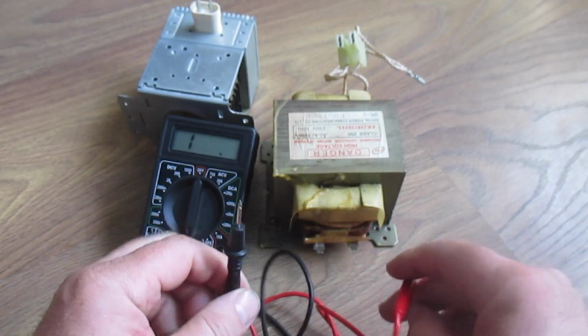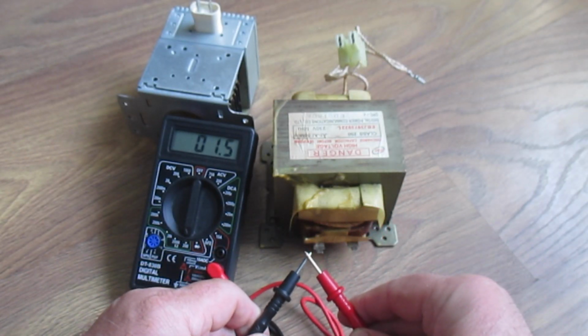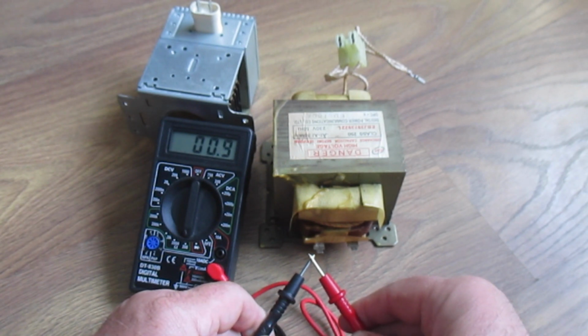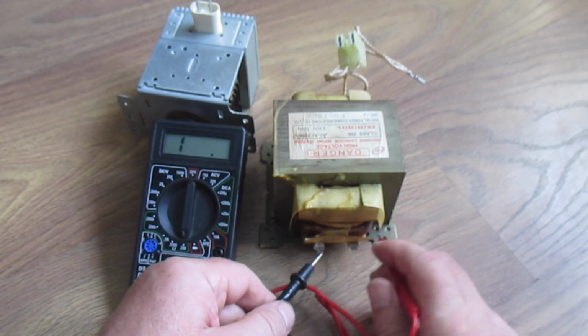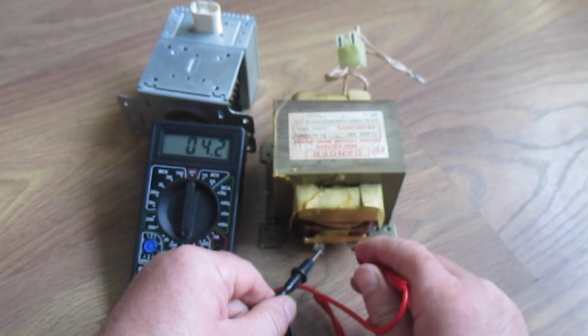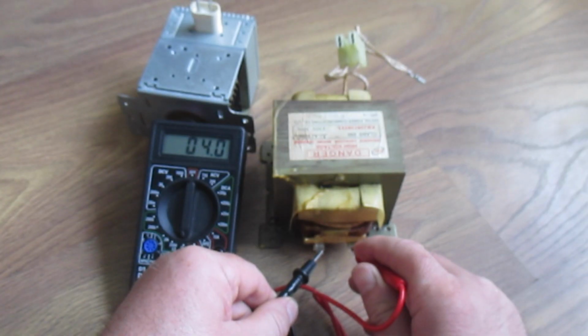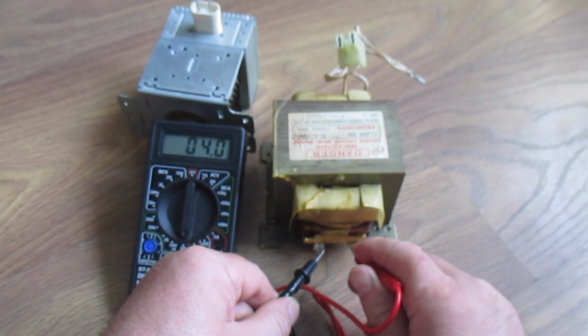Now set the multimeter to 200 ohms. Check the probes. Everything is fine. Now these two contacts of the primary winding, the reading is 4.1 to 4.2 ohms. The parameters are normal. Acceptable readings are 2 to 5 ohms.